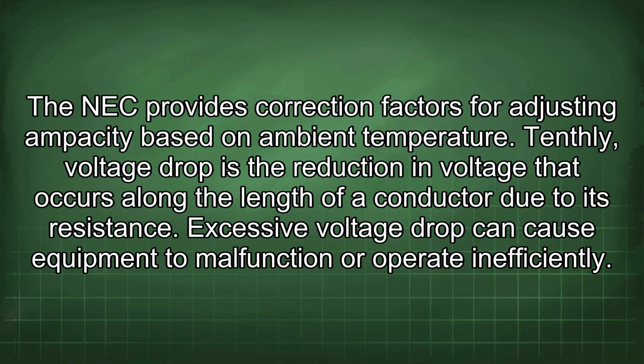Tenthly, voltage drop is the reduction in voltage that occurs along the length of a conductor due to its resistance. Excessive voltage drop can cause equipment to malfunction or operate inefficiently.